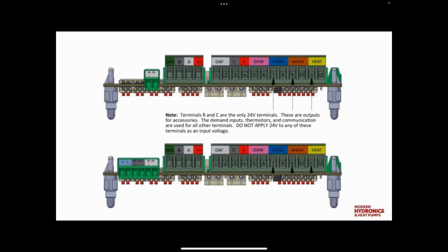Yeah, and from a controls perspective, having this be a function inside the heat pump where you're sending out the modulating signal, there's no external control that's needed. And you have full control over the settings on that boiler, or how aggressively or not you want to run the backup. It's kind of a game changer. We carry over a lot of this same functionality with our air to water system.